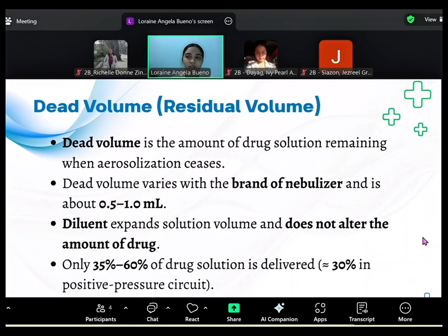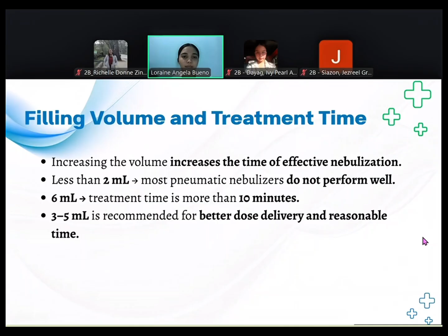Filling volume and treatment time. Increasing the volume increases the treatment time and efficiency of the nebulizer. With less than 2 ml, most pneumatic nebulizers don't perform well, and at 6 ml treatment time is more than 10 minutes. 3 to 5 ml is recommended for better dose delivery and reasonable time. Increasing fill volume increases inhaled efficiency and the dose to the patients. The approved label dose includes the fill volume used in clinical trials approved by FDA. Increasing fill volume should not be done without consulting the prescribing physician.